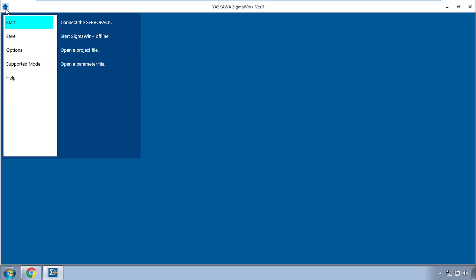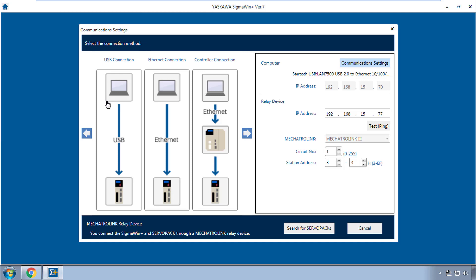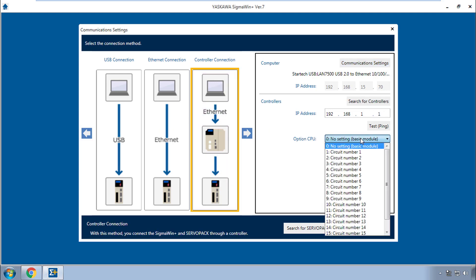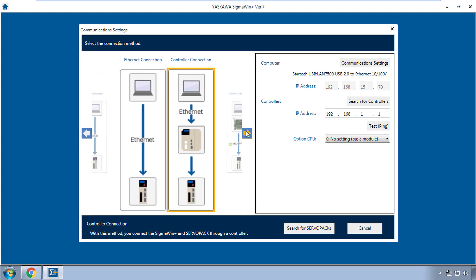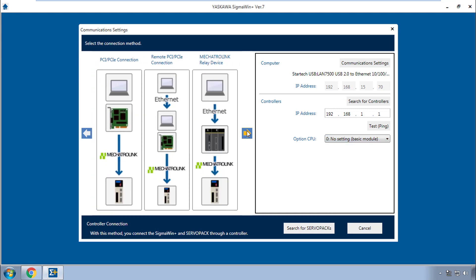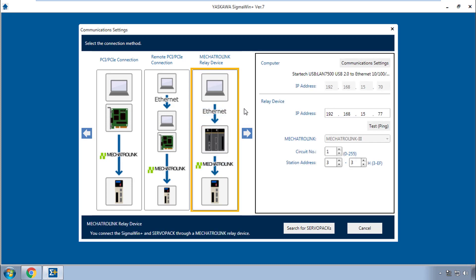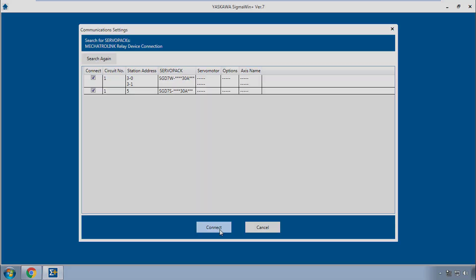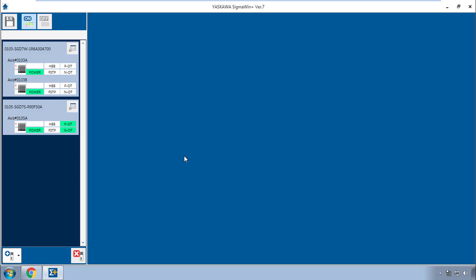I'll go here to connect the servo pack and it's not a direct USB or Ethernet connection to the servo pack and it's also not a controller connection because this implies the standard MP series controllers. Instead, it's the last option here Mechatrolink relay device and here I have set the IP address of the computer, the controller, I can test this connection and down here under Mechatrolink the station address or the nodes that I want to connect to. Search reveals the axis connected to the MP3300 IEC. I'll connect and I'm online with all three servo packs in Sigma Win Plus version 7.